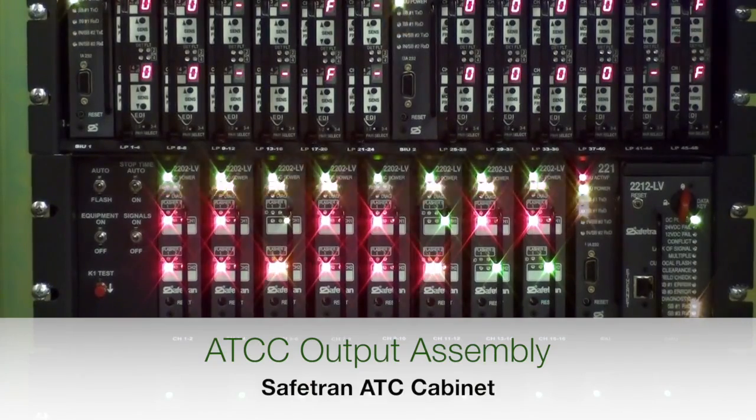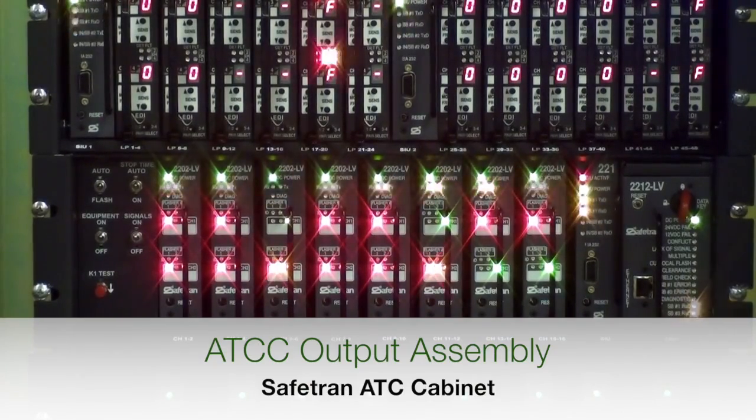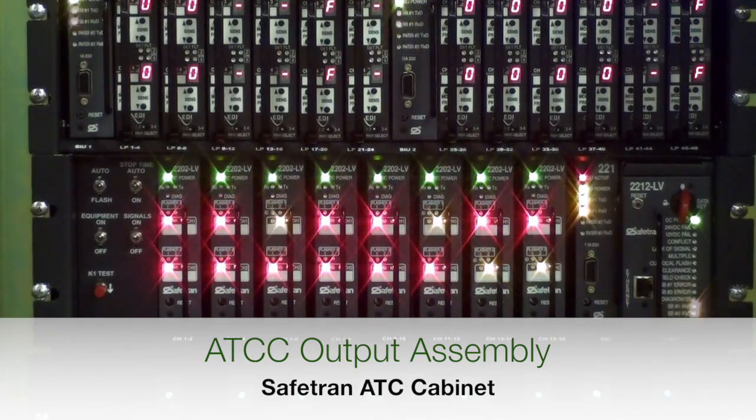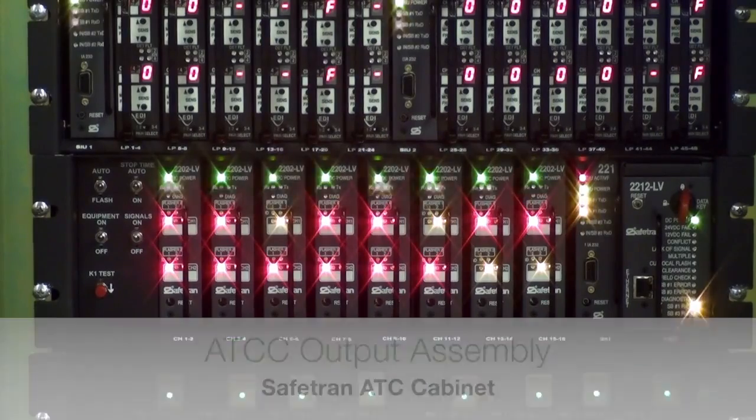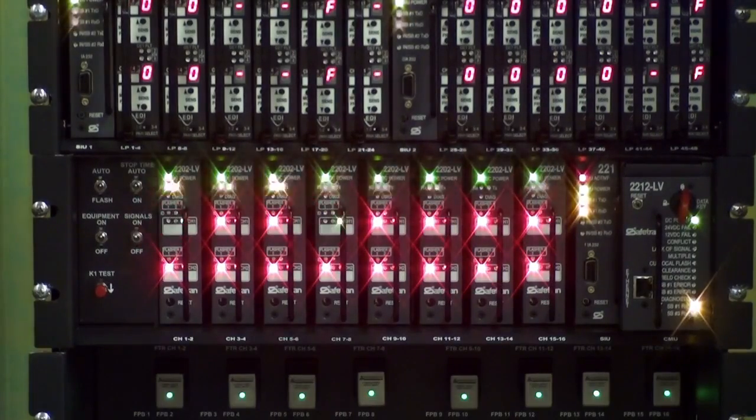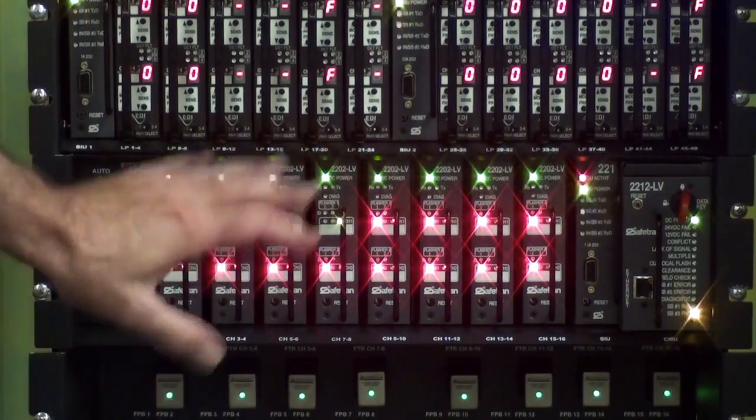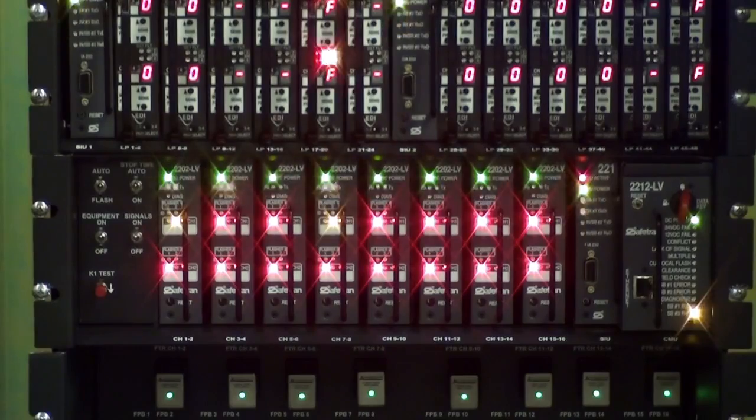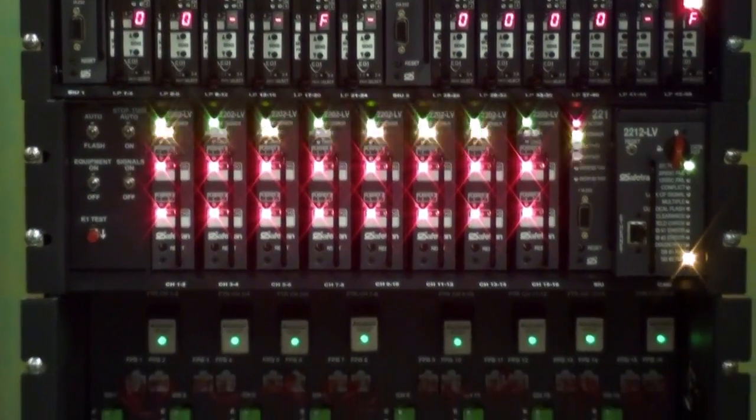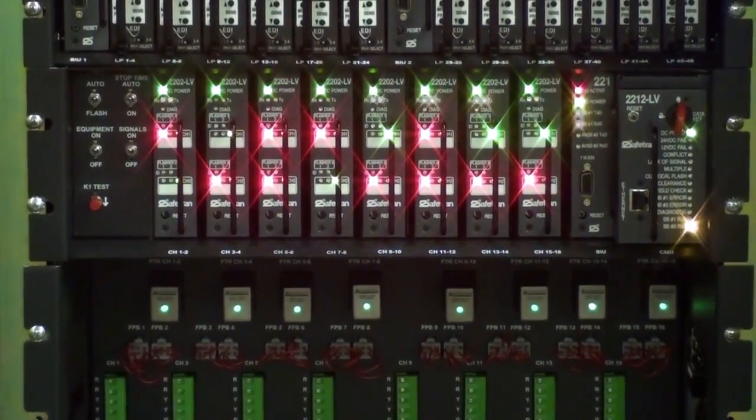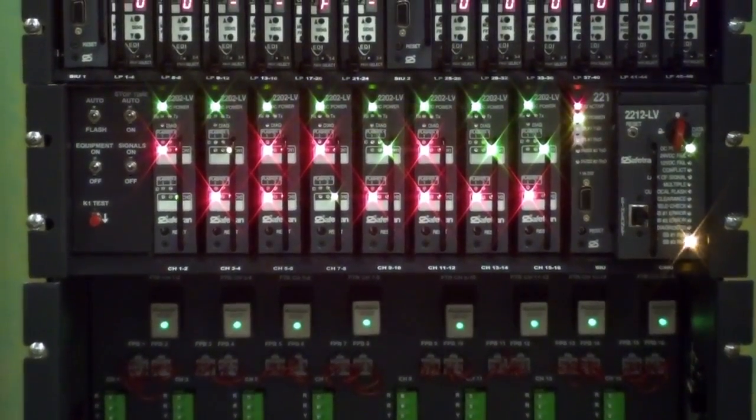The ATC cabinet supports up to 32 output channels. The new design replaces the standard large single-channel load switches with new dual-channel high-density switch packs, or HDSPs. Each SafeTran output assembly houses up to eight HDSPs, providing 16 output channels in a three-unit or three-U rack space. The user can install up to two output assemblies in the ATC cabinet.